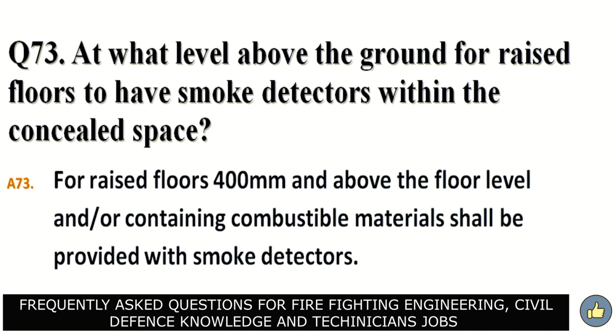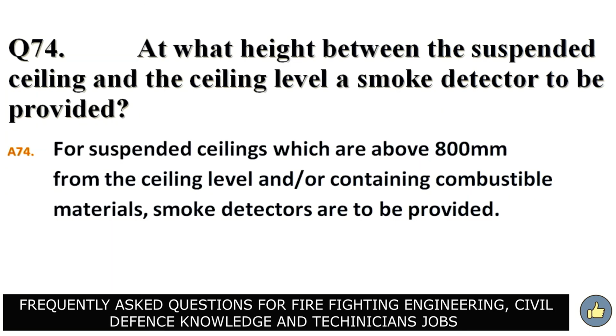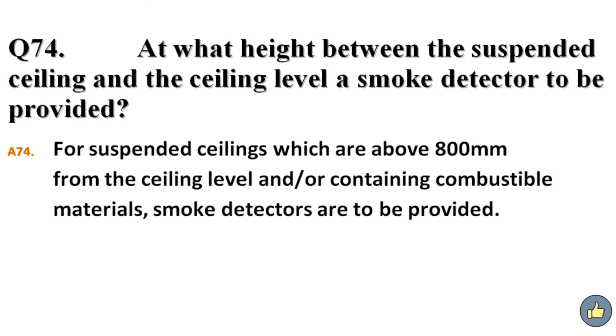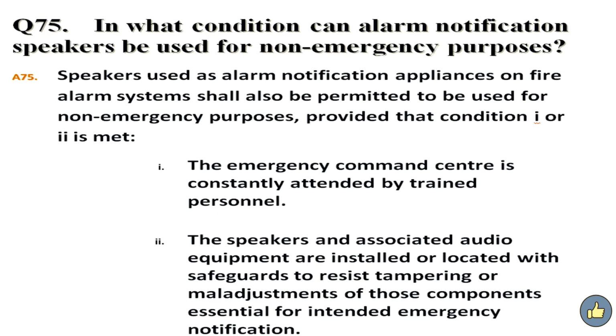At what level above the ground for raised floors are smoke detectors needed within the concealed space? Answer. Raised floors 400 mm and above the floor level and/or containing combustible material shall be provided with smoke detectors. At what height between the suspended ceiling and the ceiling level is a smoke detector to be provided? Answer. For suspended ceilings which are above 800 mm from the ceiling level and/or containing combustible material, smoke detectors are to be provided.